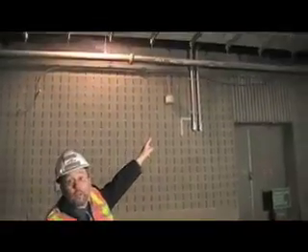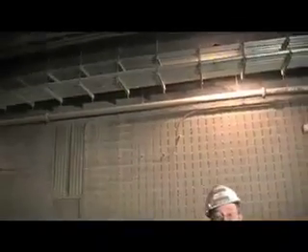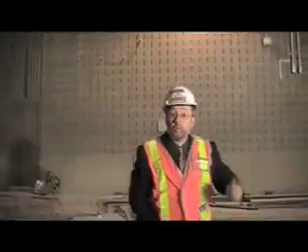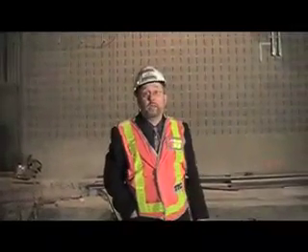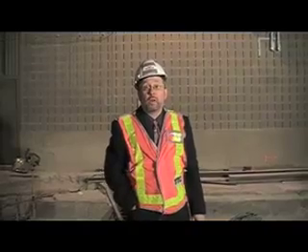That's what you see up there — those are new conduits, and the wires that power the station are within those conduits. The wires that were in the concrete here had to be removed and taken up to the top end of the station and routed around the station to avoid the expansion joint work. That was $400,000 worth of unanticipated work.